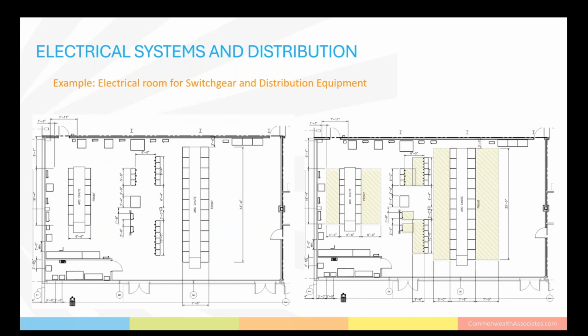This is the electrical room that I mentioned in the life safety egress slide. It shows some of the key spacing requirements to be considered. For circuits, this room has been designed for a 13.8 kV system, 8 circuits, and a total of 11 sections. The arrangement is based on 3 480 volt MCCs, 6 low voltage distribution panels, and a 6-section 480 volt switchgear. Minimum NEC clearances always need to be observed. In addition to those clearances, the designer needs to ensure that there's adequate space for operational and maintenance requirements.